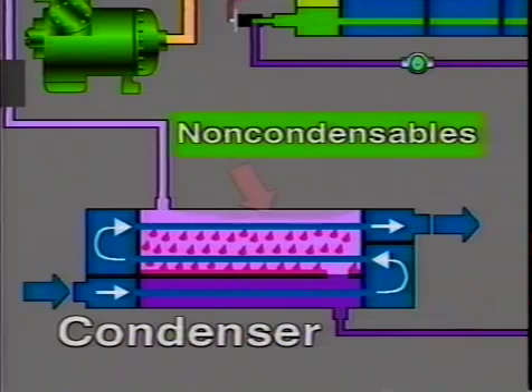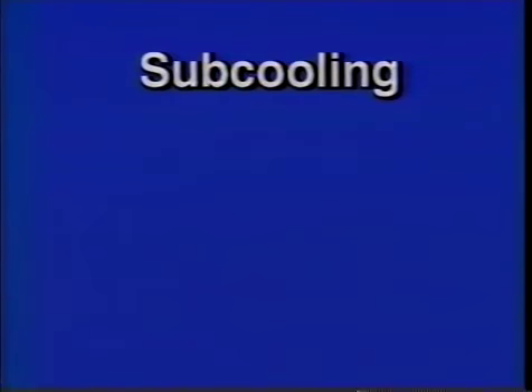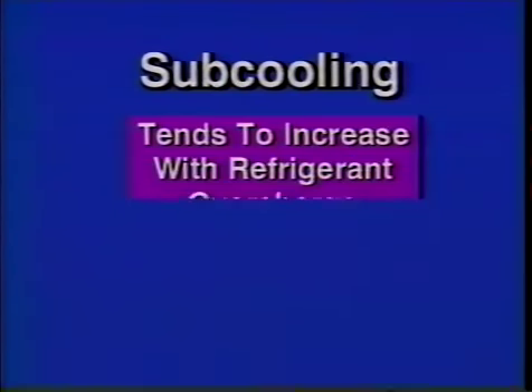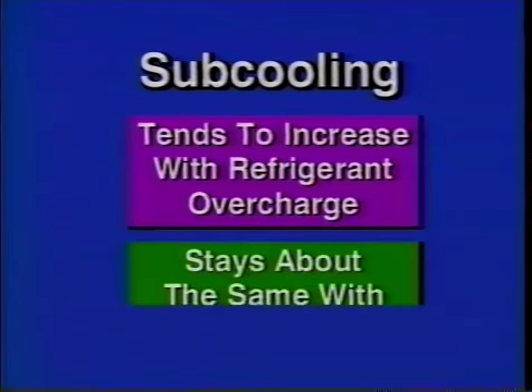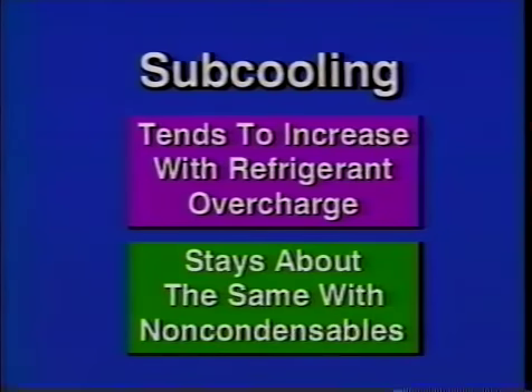Non-condensables are air or other unwanted vapors that do not condense in the condenser. They reduce effectiveness of the condenser and cause the head pressure to rise. The symptoms of non-condensables are similar to those of the refrigerant overcharge. You can often distinguish the two by checking the liquid subcooling, which tends to increase with the refrigerant overcharge and stay about the same with non-condensables.